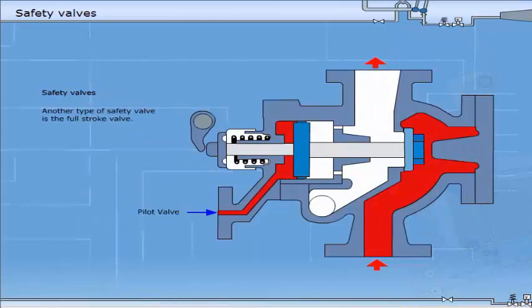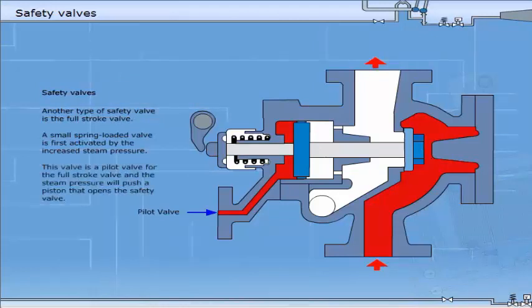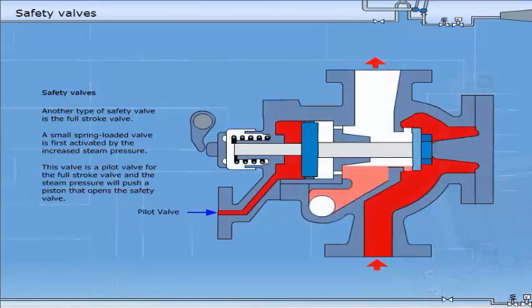Another type of safety valve is the full stroke valve. A small spring loaded valve is first activated by the increased steam pressure. This valve is a pilot valve with a full stroke valve, and the steam pressure will push a piston that opens the safety valve.